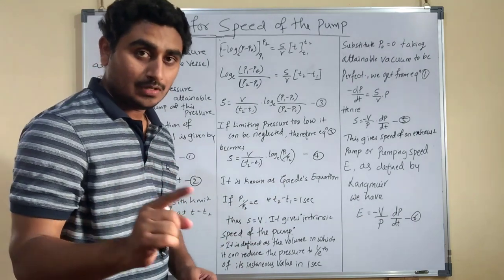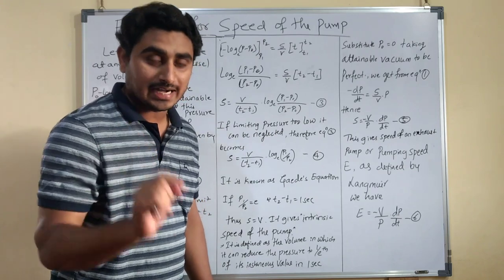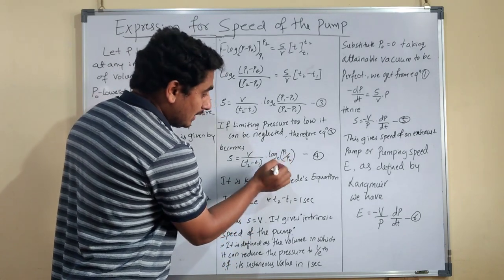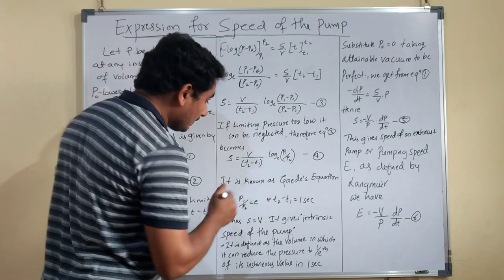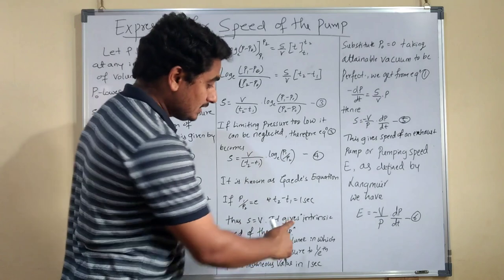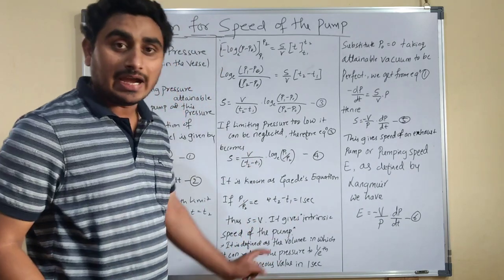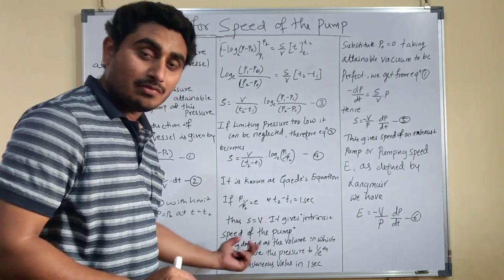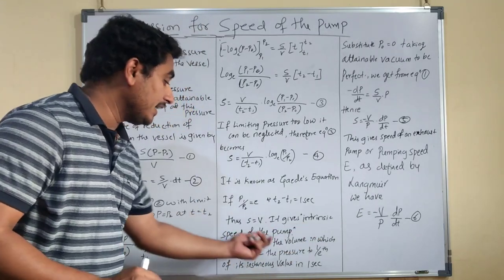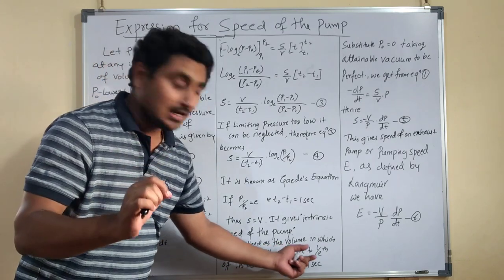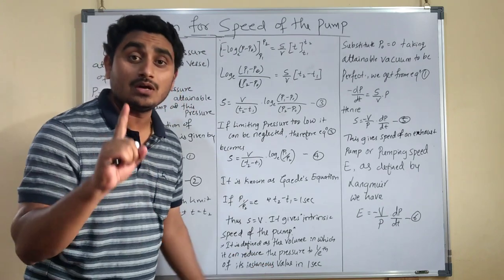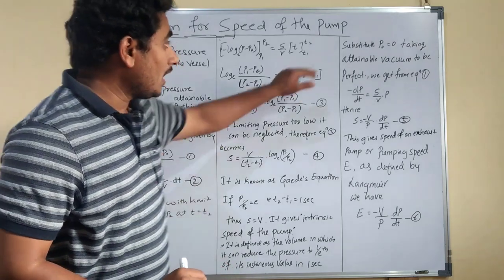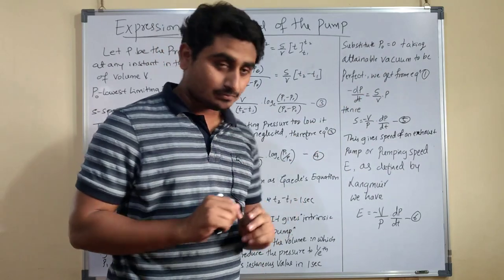If P1/P2 = e and (t2 − t1) = 1 second, substituting into equation 4: log(e) = 1 and (t2 − t1) = 1, so S = V. This gives the intrinsic speed of the pump, defined as the volume in which it can reduce the pressure to 1/e of its instantaneous value in one second.